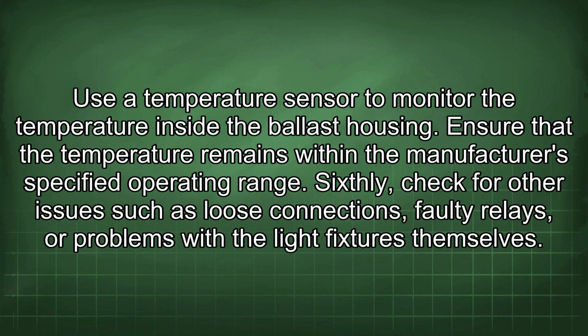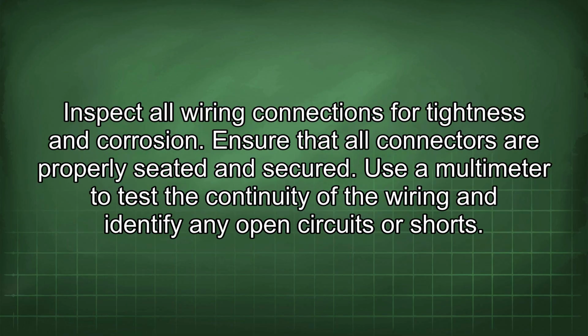Use a temperature sensor to monitor the temperature inside the ballast housing. Ensure that the temperature remains within the manufacturer's specified operating range. Sixthly, check for other issues such as loose connections, faulty relays, or problems with the light fixtures themselves. Inspect all wiring connections for tightness and corrosion. Ensure that all connectors are properly seated and secured.